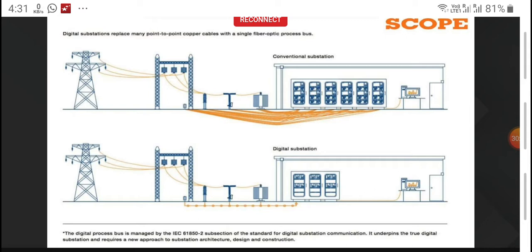You can see that the above picture represents the SAS-based or conventional substation, where a lot of cables go from the transformers, feeders or breakers to the control panel and control room, where the control room is full of auxiliary relays, protection relays and backup relays. All these things are used in the control system. But when you see the digital substation in the picture below and compare it with the top picture, this copper cable is completely eliminated, and a single optical fiber cable is laid from the substation to the control center, and all of these are connected with Ethernet switches or some other bus.